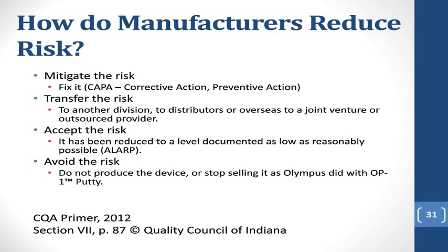So even though it's the same type of device and it's used for the same situation, which is to monitor the heart rate of the baby during birth, the two manufacturers had two different approaches to identifying the risk and even mitigating the risk.